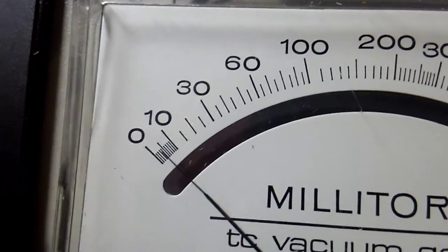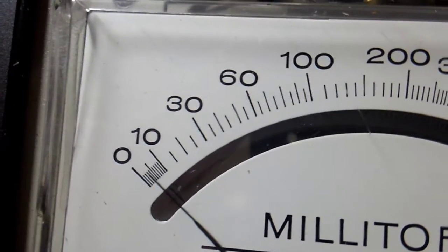Of course this gauge is only good for an accuracy of plus or minus twenty percent. And the turbo pump is now at speed, that's that second green LED. I don't know if I'll be able to get the sound of the turbo pump in here into the microphone.